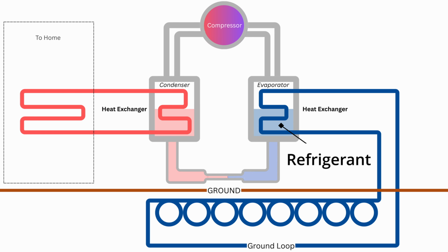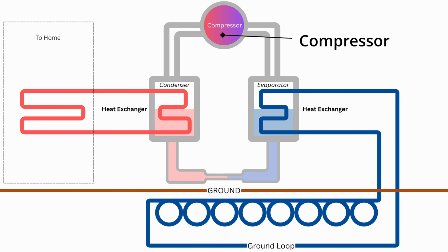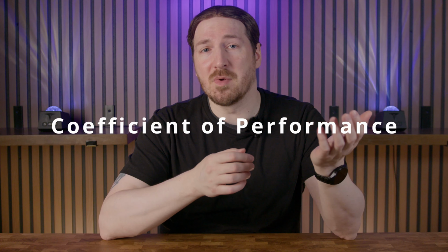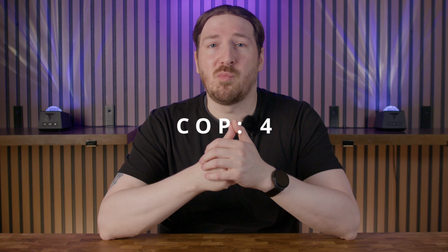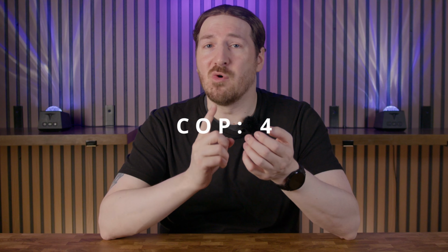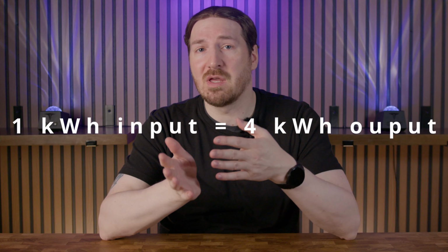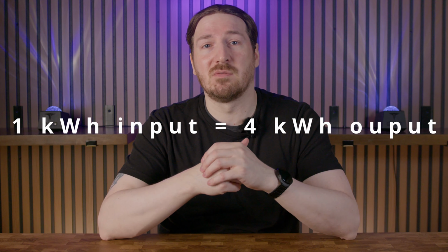Inside the heat pump, the liquid passes through a refrigerant with a really low evaporation point, which absorbs the heat and turns it into a gas. The gas then goes into a compressor and is compressed, which raises its temperature, and then it transfers that to heat the air or the water in the home. This process can also be reversed to cool the home. Heat pumps are rated by their coefficient of performance, or COP. A COP of 4 means that for every 1 kilowatt of electricity, 4 kilowatts of heating or cooling is produced.